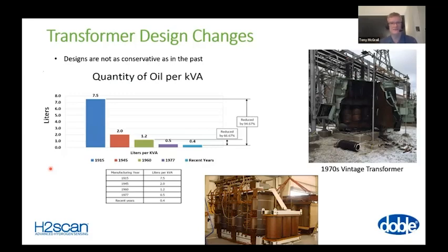It's a 1970s design, which they made smaller, but the oil got forced through the transformer and would pick up static charge as it flowed. And the 7 million series was famous for what's called static electrification. A bit like having a Van de Graaff. The oil would go fast through some parts, it would pick up charge, it would deposit elsewhere, it would build up, then it would discharge and eat away the insulation. So we've got to be careful that we understand the chart as it relates to the cooling of the oil and the ability of the transformer to cool.